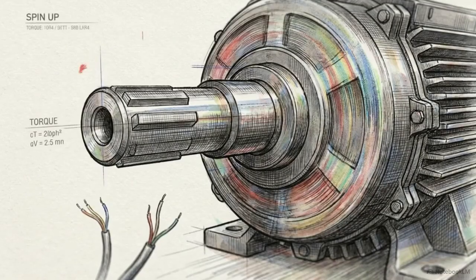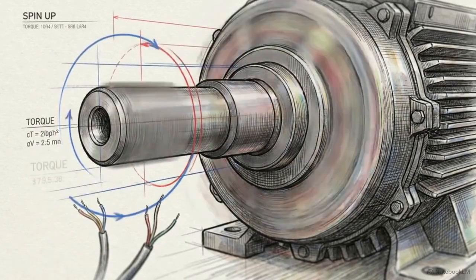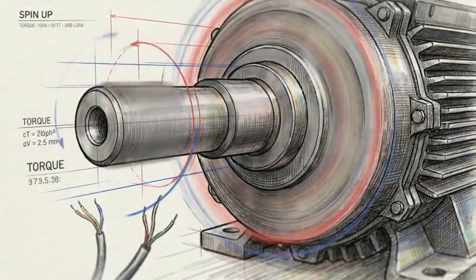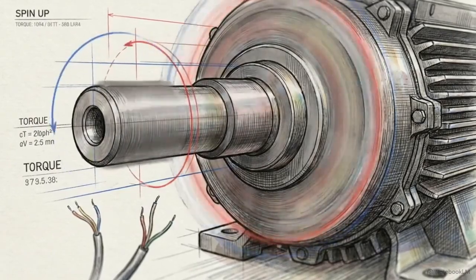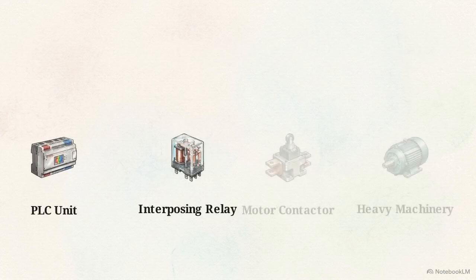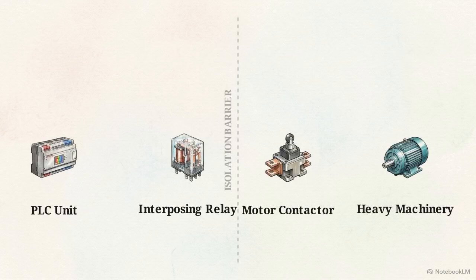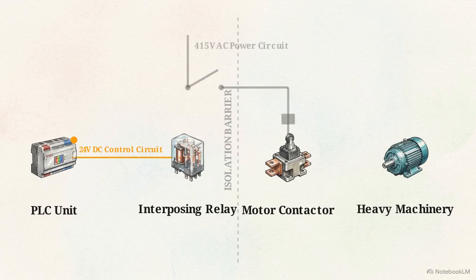The PLC uses highly sensitive, low-power microelectronics that cannot directly handle the massive voltage and current required to spin heavy industrial motors. This schematic illustrates the solution: interposing logic. We wire the PLC's 24-volt digital output to the coil of a small intermediate component called a relay. When the PLC output turns on, the 24-volt signal energizes an electromagnet inside the relay. That magnetic field physically pulls a set of heavy metallic contacts closed, bridging a totally separate high-voltage circuit.